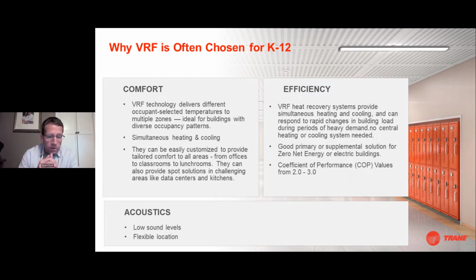Nowadays, what we're seeing in the Northeast is the desire for a lot of zero net energy or electric buildings. You have one of three options: electric boilers, or some sort of electric heat recovery chillers, or a VRF system. VRF systems are also very efficient, with coefficient of performance values anywhere from 2 to 3, depending on the season. Another reason why we like VRF is the acoustic properties.